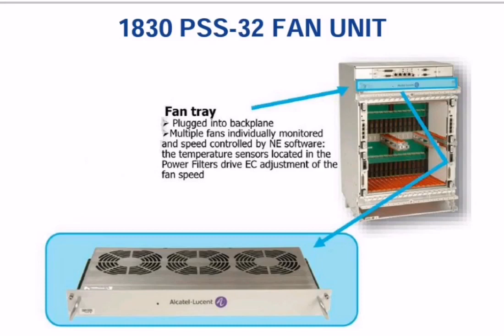Multiple fans are individually monitored and controlled by software, and temperature sensors are also located in the power filter that adjust the fan speed. We also have a threshold value for the temperature, like 25 degrees centigrade. These fans are really helpful for keeping our equipment cool so that our temperature does not exceed the limit.